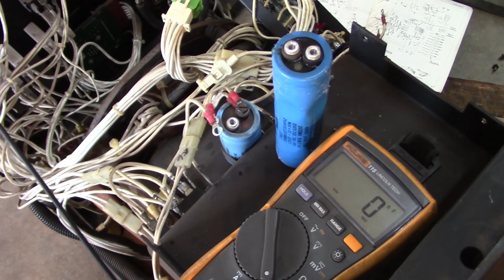I've got the multimeter set up to test capacitance, and it reads nothing, OL. If I check this other capacitor down here, it's reading 240-something microfarads, so that one's right on the money. This one, nothing. So if I switch this over to ohms - oh, that's continuity. Either way, it's a bad sign. Yeah, 0.1 ohms across an electrolytic capacitor - I think we've got a problem.